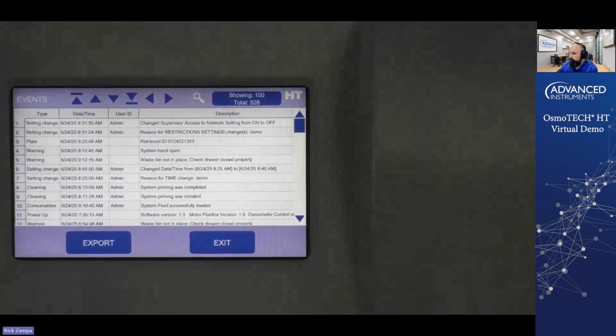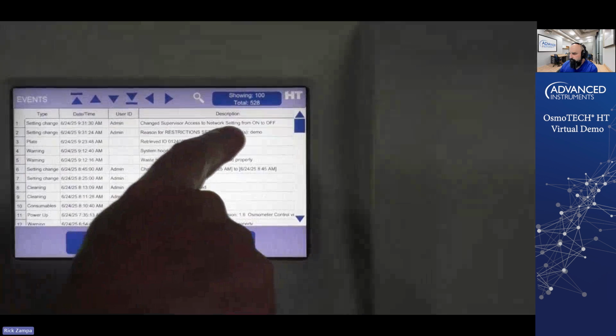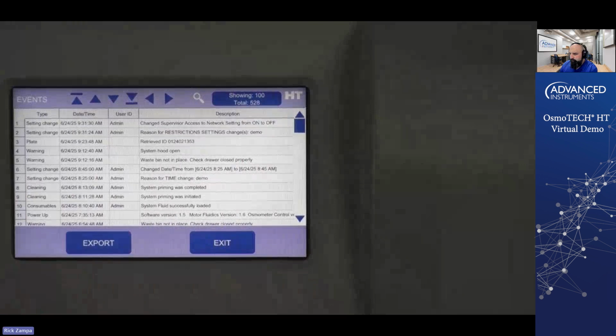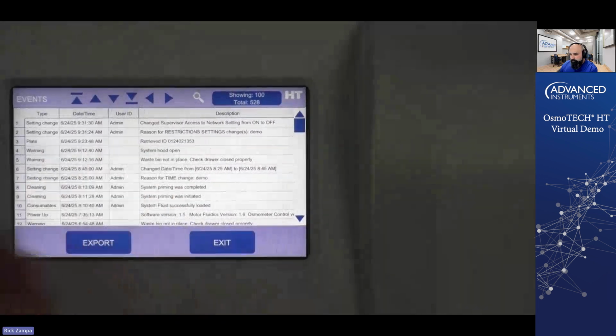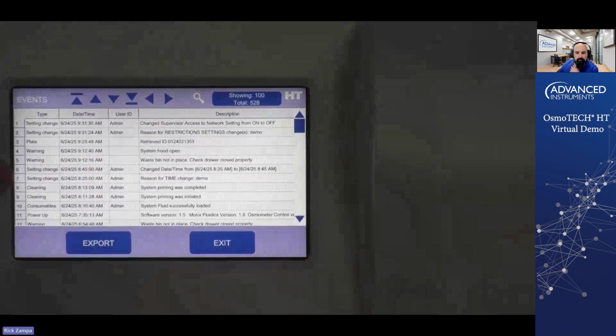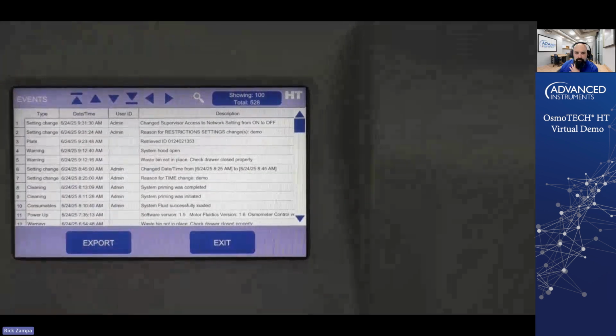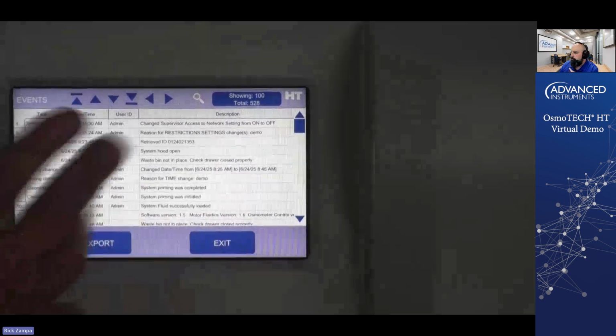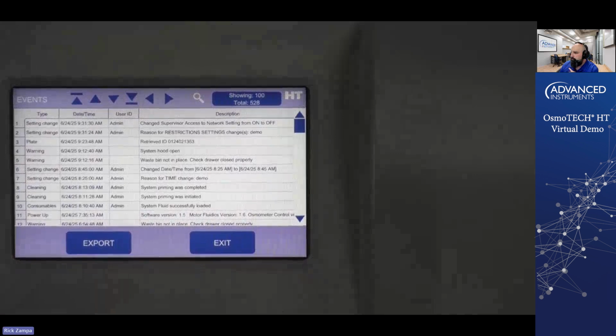So this is our events database. What you can see here are the 2 changes I made. I changed the supervisor access to network setting from on to off, and it tells me why I made that change. You can also see that we retrieved the plate that we ran there. The system hood was open when I opened it before I did that. The waste bin was open. So it tells you everything that's gone on in the instrument and what's happened, all changes, all potential, I don't want to call them errors, like the doors opening. It shows you when consumables have been changed and things like that. So everything is stored here for the instrument so that you always know what's happened to the instrument if you're looking at any particular issues going on.